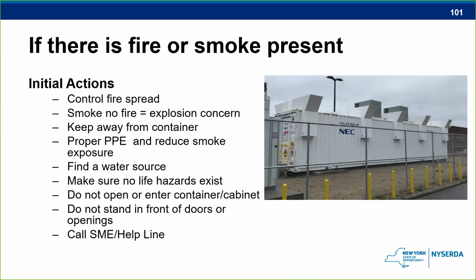So when there's smoke and no fire, incident commanders have to think of an explosion concern right there. What we have noticed in a lot of the testing is that when we heat these batteries up and they're not on fire yet, they will produce a white smoke. And that white smoke is that flammable cocktail that I mentioned before. That flammable cocktail is made up of a lot of different hydrocarbons, and the biggest part of the mixture is hydrogen.